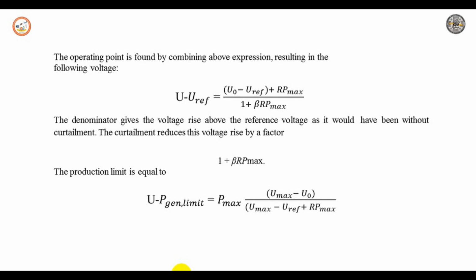So the above expressions for voltage and production limit have been derived for one large unit which is connected to the feeder. However, it can easily be shown that the expressions also hold for more units connected at the same location. In this case, P gen and P max are the sums of the values for the individual generators. The curtailment of each individual generator is by the ratio of their maximum production. For example, if the above equation produces a reduction of 25% of total production, each unit would be reduced by 25% compared to maximum production. This assumes that each generator produces exactly the amount to which it is curtailed.